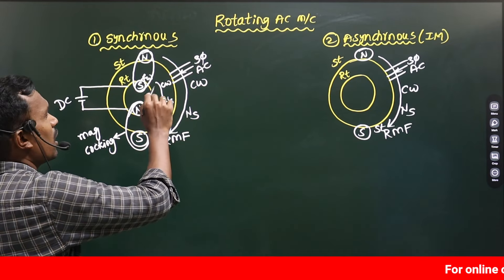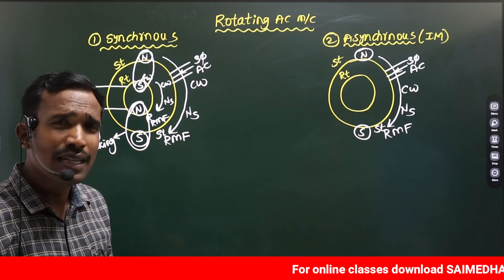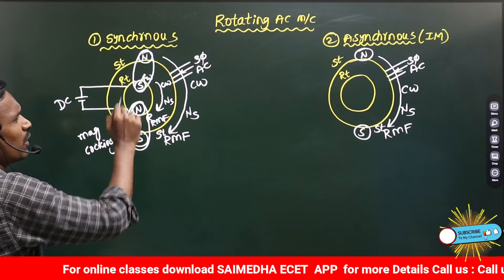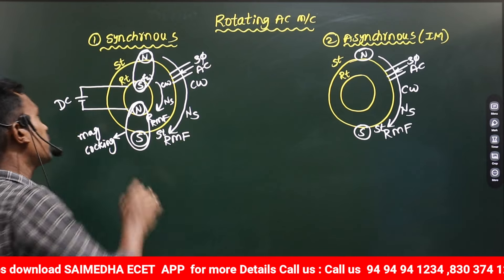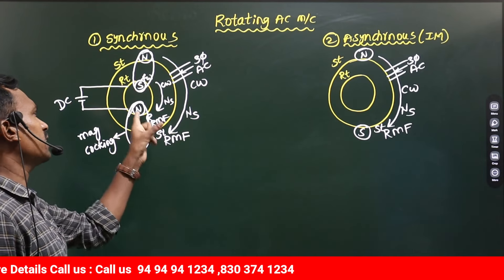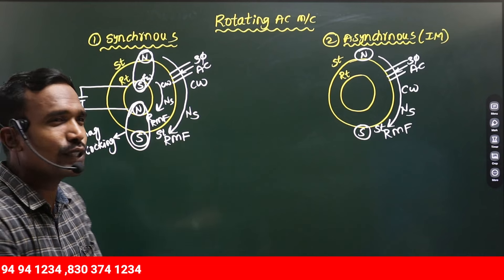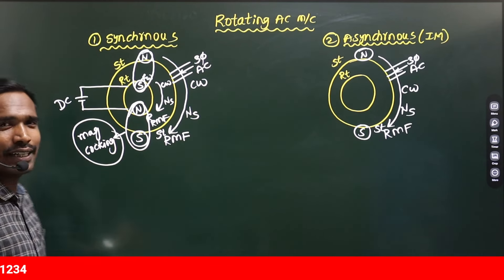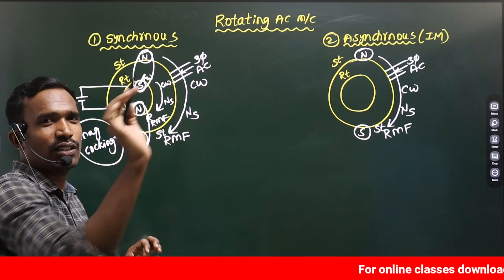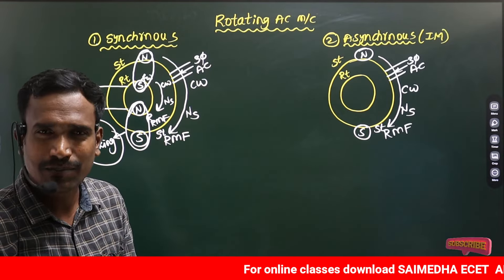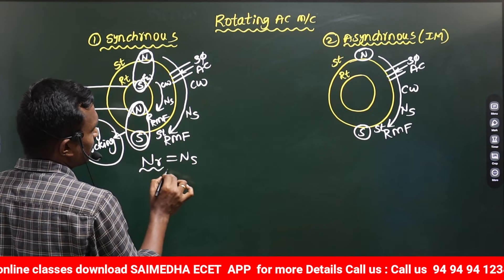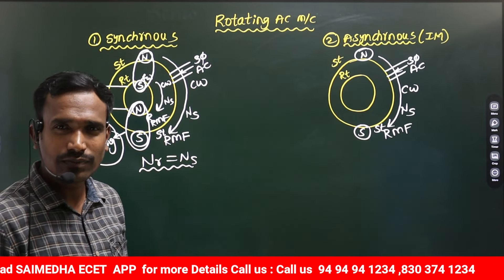Due to this magnetic locking, the rotor constantly rotates at Synchronous speed. The Synchronous motor is not a self-starting motor — we need to first rotate the rotor in the same direction at the same speed, then give the DC supply. When poles are created, attraction force develops and converts into magnetic locking, after which the rotor rotates in clockwise direction at Synchronous speed.